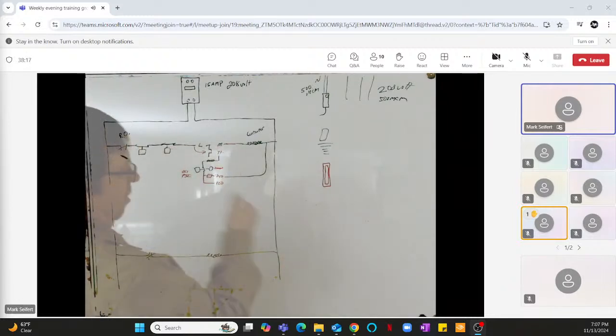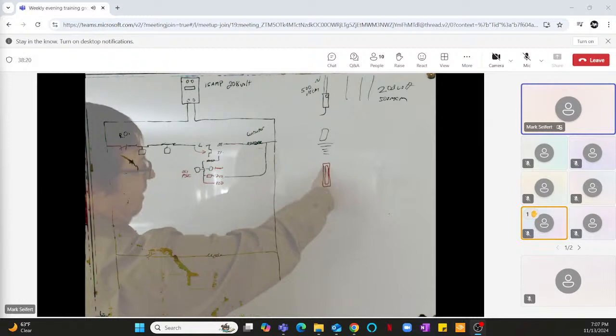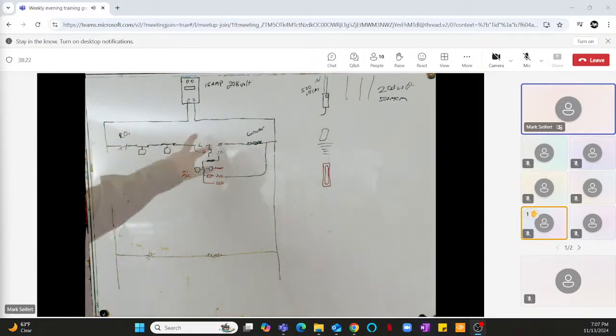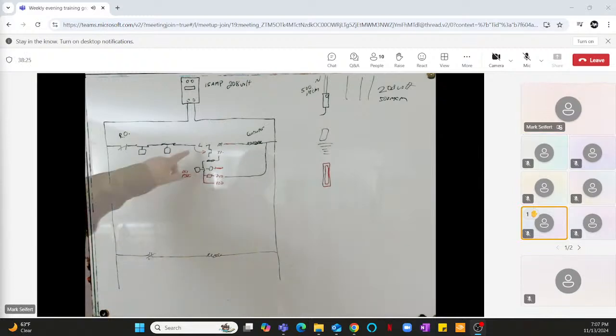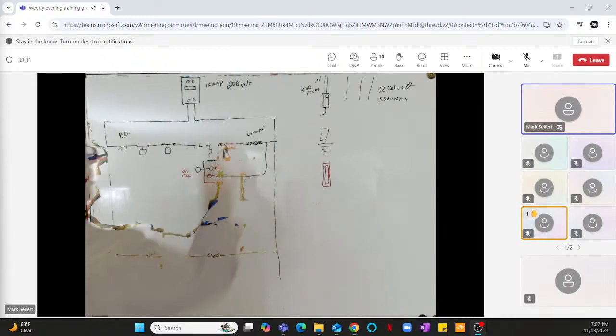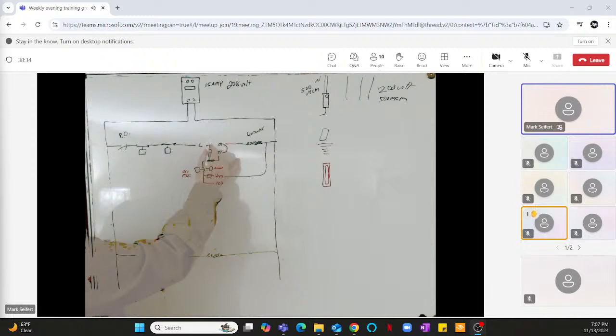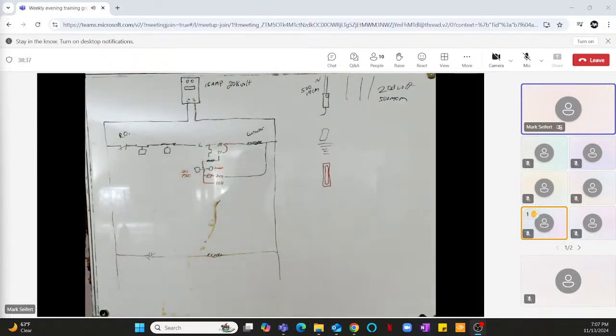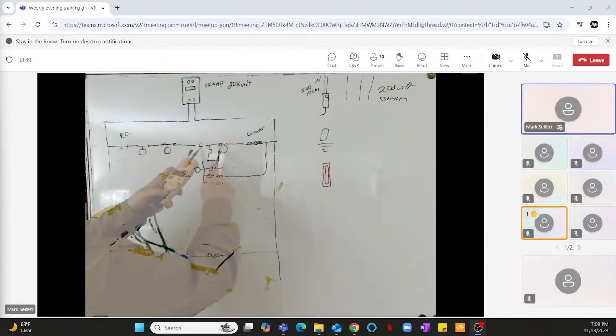If you ever come across one where you're like, L and M is open, but it won't reset, and it's an old school one, put your thumb on that little resistor. If it's hot, it's because it's crossed right there. So you go ahead and you uncross it. Now you got your jumper back there, and your circuit is like that. This is no different than any of the other ones. Always check it between L and M. If you've got 208 volt there, the switch is open.